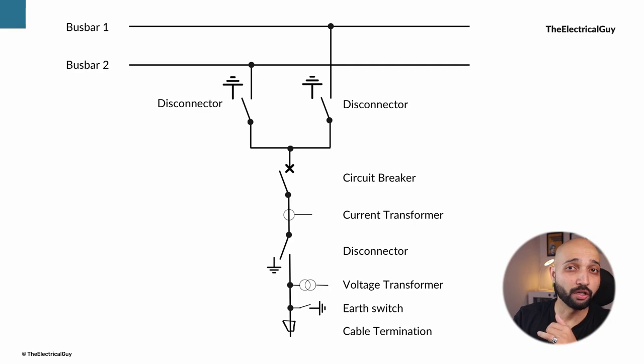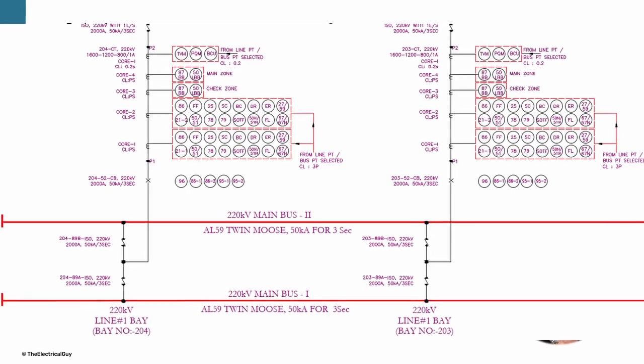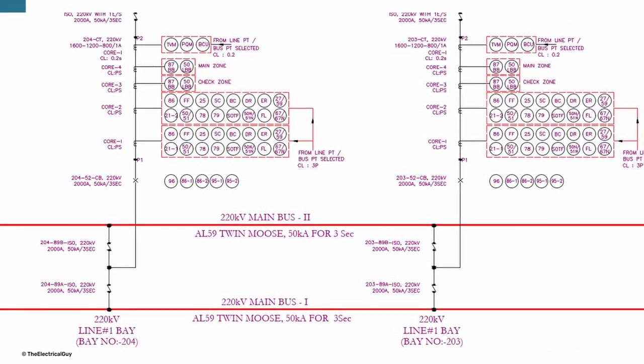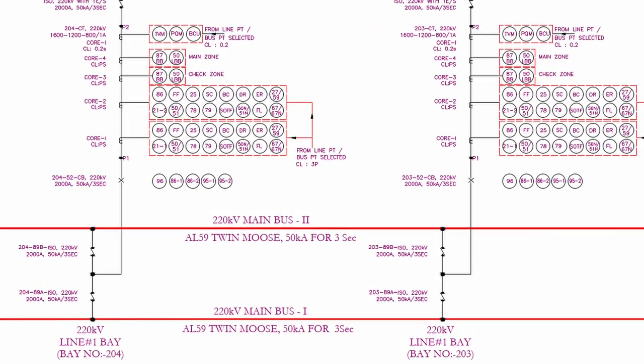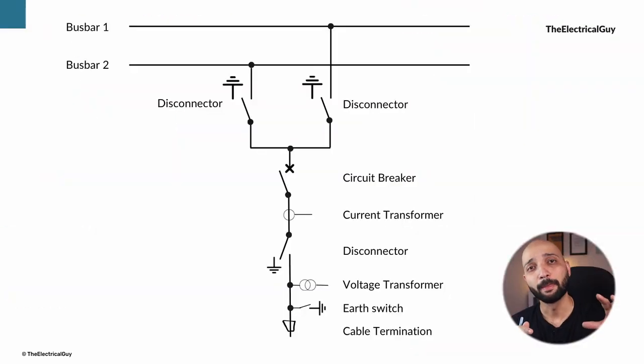It shows the correct location of CTs for different functions, the summation of CT windings, overlapping of protection zones, selection of voltage transformers, etc. can all be easily checked on the single line diagram. Details such as rated voltage, CT ratios, current ratings of switchgear and many other things are also included on these single line diagrams.